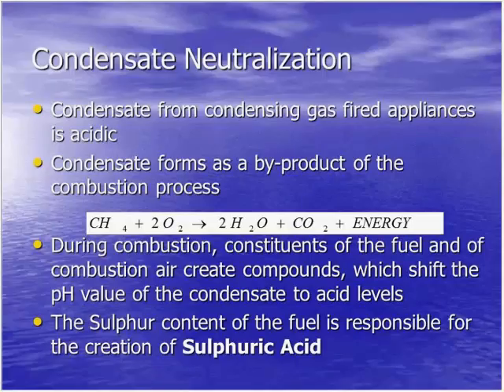But during combustion, there's constituents of the fuel and of the combustion air that create compounds which will shift the pH value of the condensate to acidic levels. The sulfur content in the fuel is responsible for the creation of a mild sulfuric acid. There's also nitrates that are responsible for some nitric acids. Typically, we see the pH range, and it depends on a number of factors, in the range of about 3.5, low threes, up to about 5.